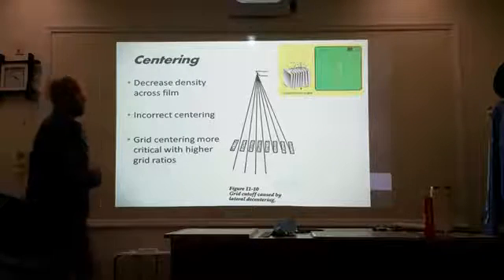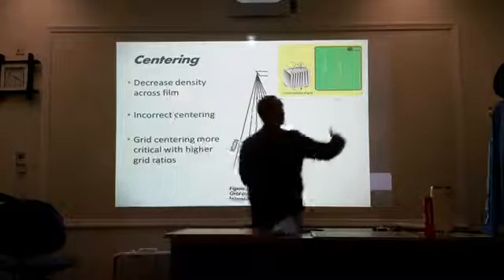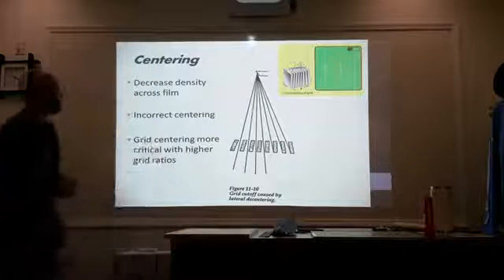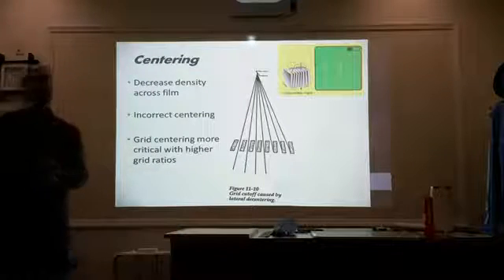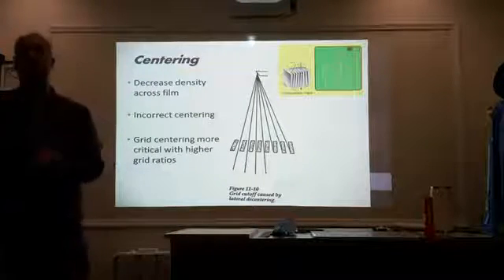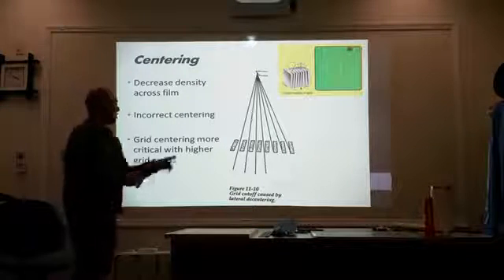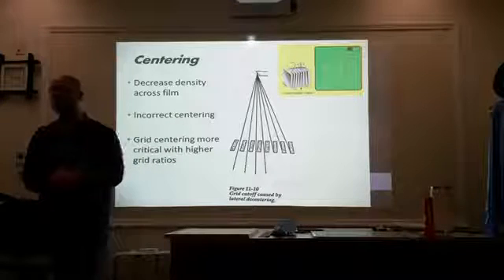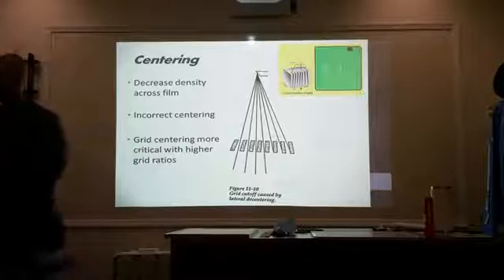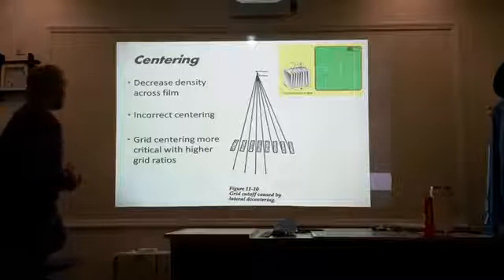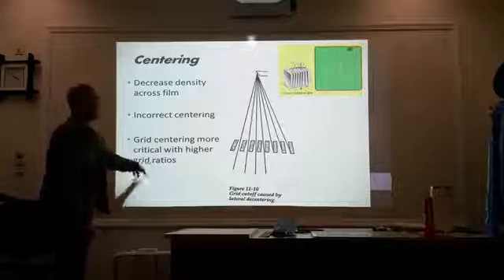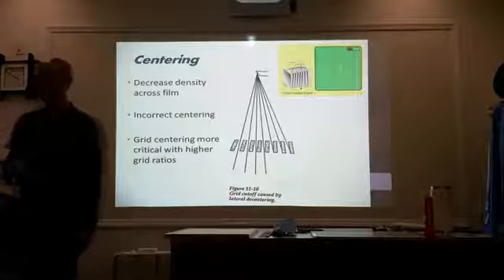Centering. Again, you want to be right in the center of your grid. If you're off-center, you're going to have decreased density across the film because your beam is divergent and it's not matching the lead strips. Centering is more critical with higher grid ratios. Narrow margin of error.